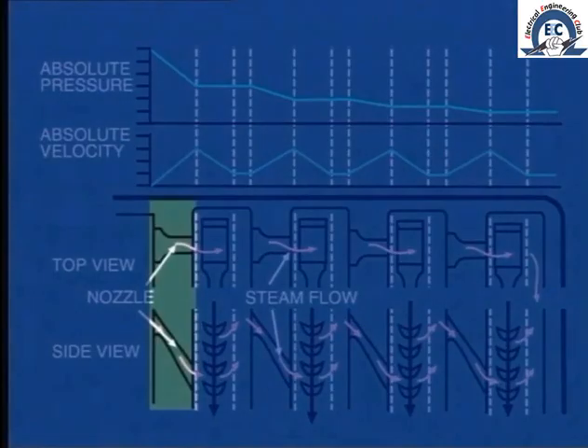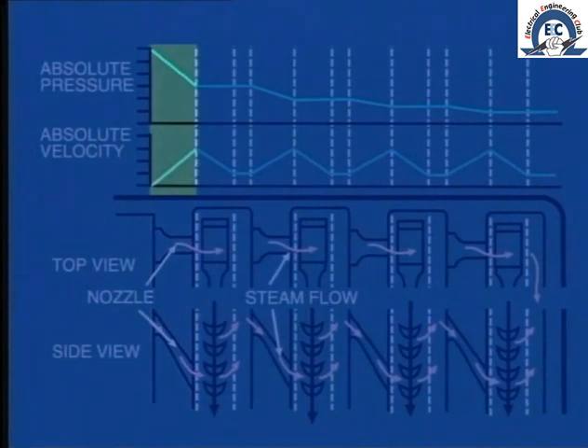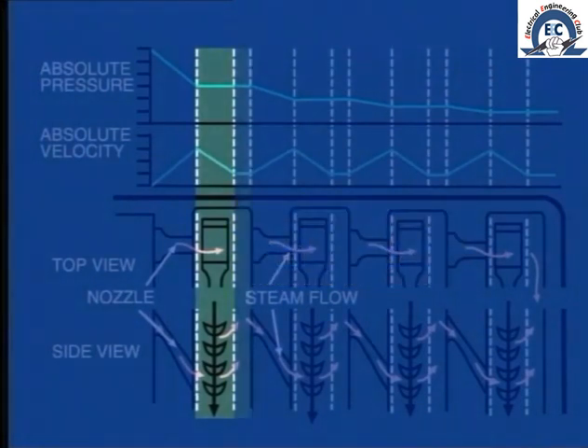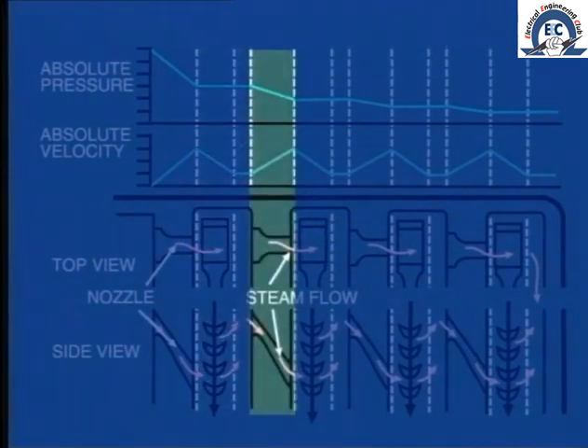As the steam passes through the first row of stationary blades or nozzles, its pressure decreases and as a result, the steam velocity increases. These changes are plotted on this graph. As this high velocity steam is directed onto the moving blade, the impulse pushes the blade forward and consequently produces rotation of the shaft. By the time the steam leaves the moving blade, it has lost much of its velocity and it then passes on through the next row of stationary blades.